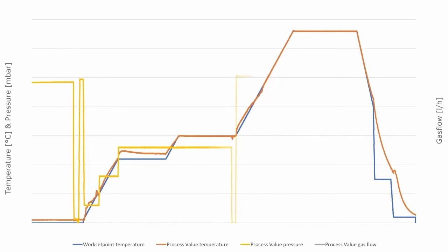Then, the furnace is filled up to perform an overpressure test. If the leakage rate during both preliminary tests is within acceptable limits, the main program will start.